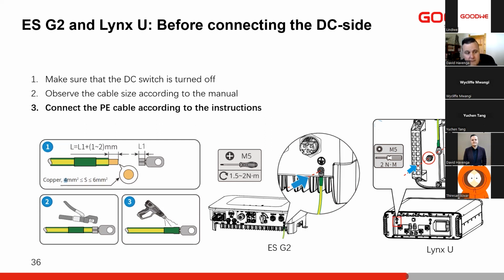It's very important. This is in the user manual: that we install sufficient grounding not only on the AC terminals but also on any metallic part. Any external metallic part should have a grounding connection, and they should all be equipotentially bonded and connected to the home's grounding. It's always good practice when installing a solar system to install some extra earth spikes as well, to make sure that should the utility's grounding fail, we do have sufficient grounding on the site.